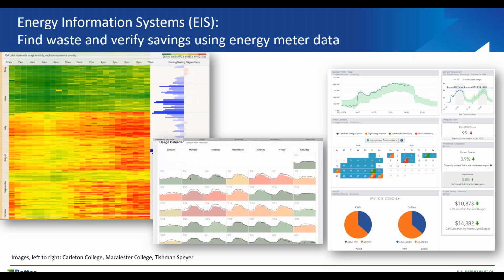In the middle, we have a calendar view color-coded to show days with high energy use relative to a modeled baseline prediction. So you don't just take a gut sense that your energy use is okay because it was hot today—this is factored in. You can have a weather-normalized prediction based on your baseline energy use and compare that to your actual daily use across the 24-hour load shape.